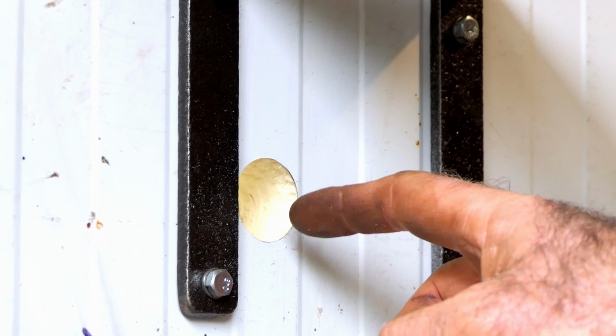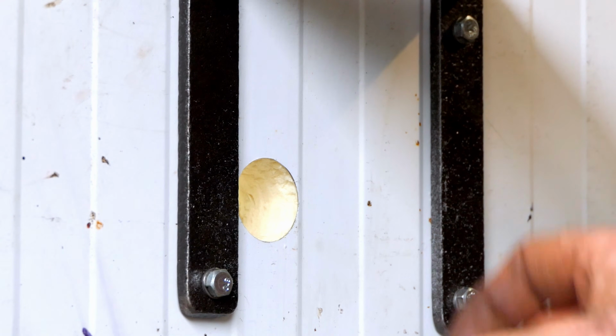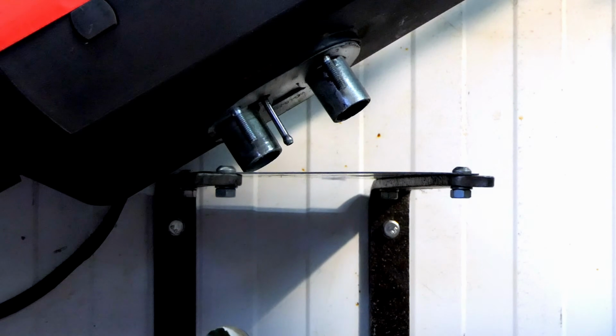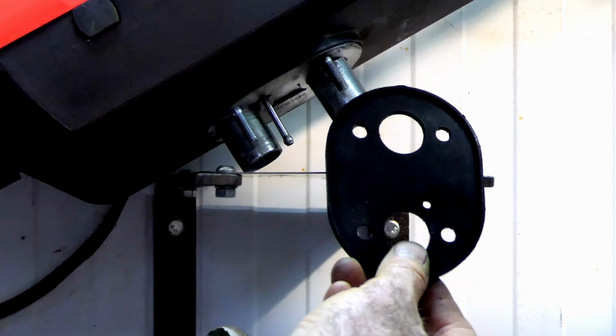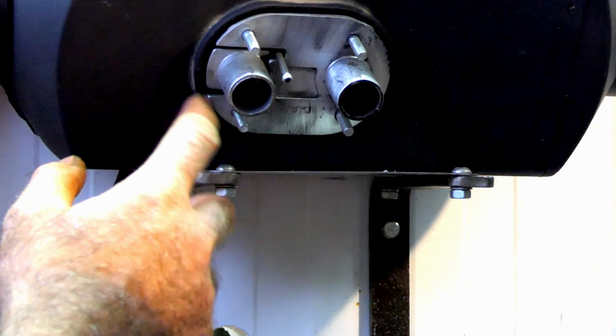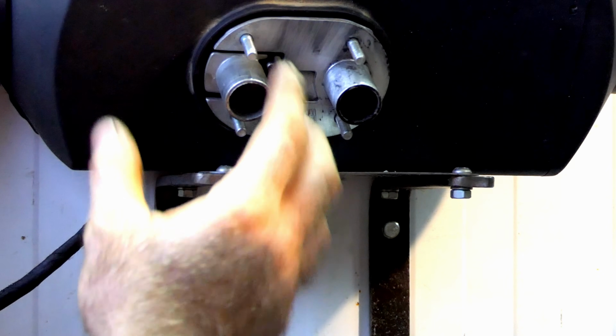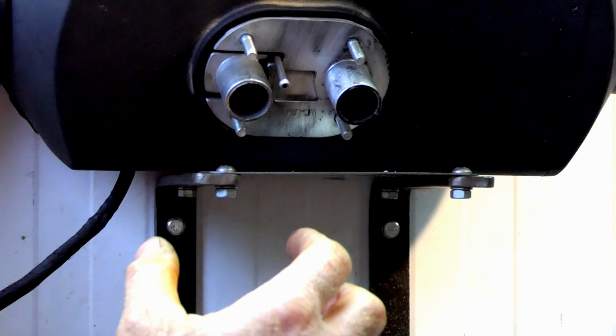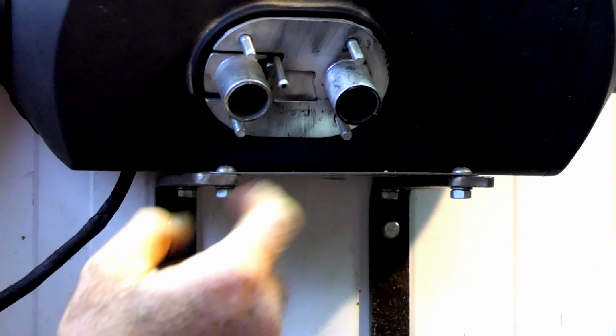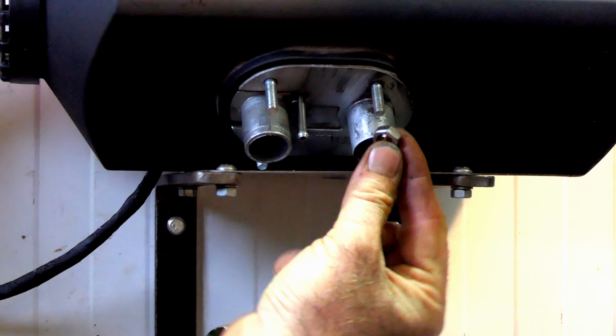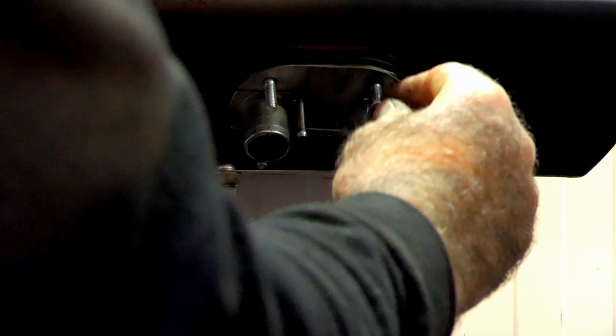For the air inlet though, I've got something very interesting to show you. Let's assemble it all together. I umm'd and ahh'd over whether to put a rubber back on it again, but in the end I've decided not to. That means a lot of air from the blower is going to escape around this hole. Because we've got the burner inside, that's not really a problem, but if this unit were outside, we'd lose a lot of efficiency. I've also decided to put some spacers there as well.